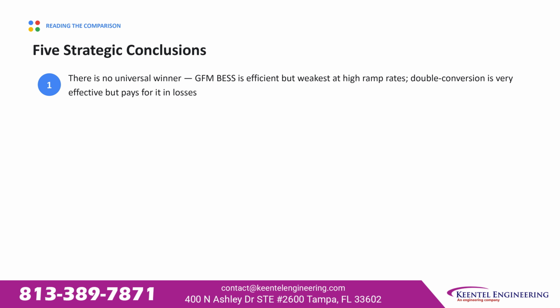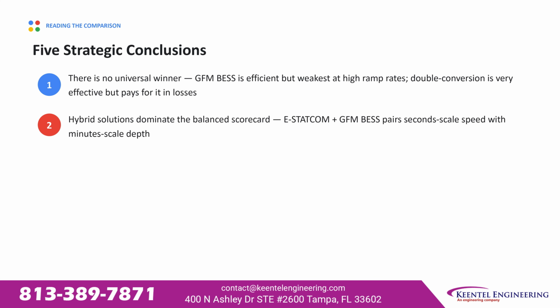Five conclusions follow from that comparison. First, there's no universal winner. Grid-forming battery storage is efficient but weakest at high ramp rates, while double conversion approaches are very effective but pay for it in losses. Second, hybrid solutions dominate the balanced scorecard. An eStatCom paired with grid-forming battery storage combines second-scale speed with minute-scale depth.